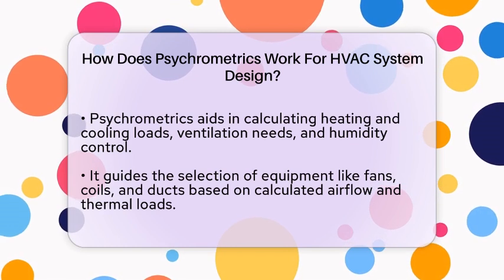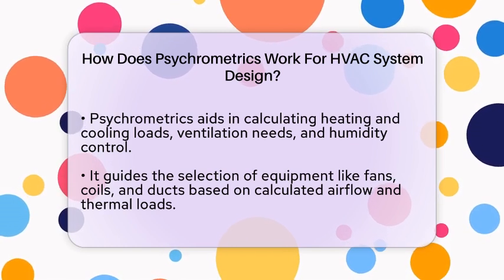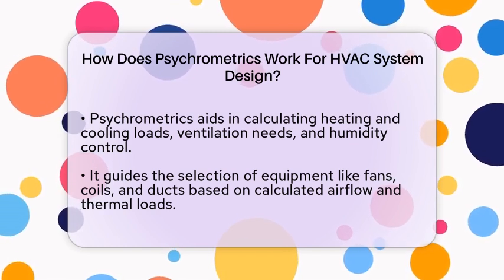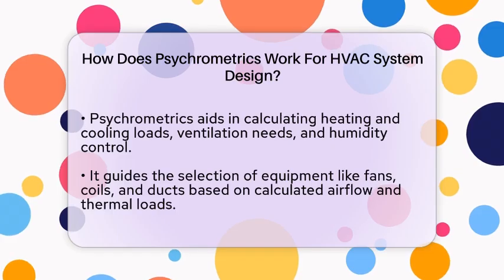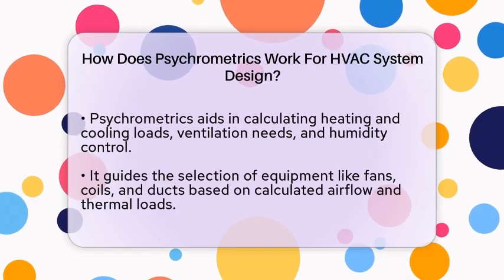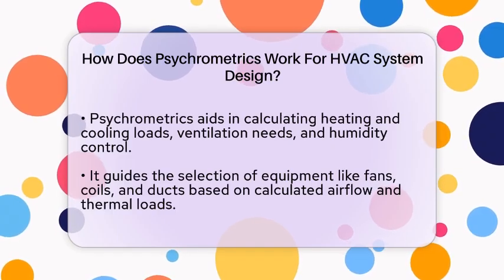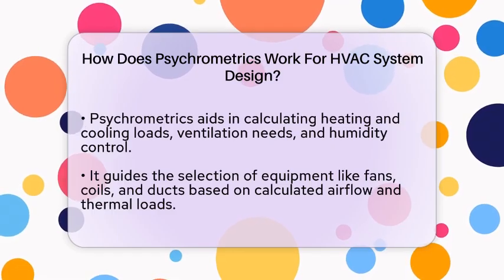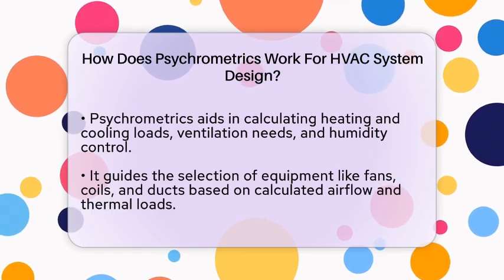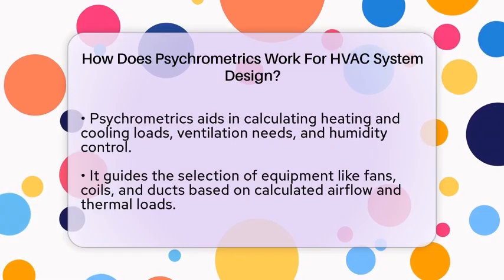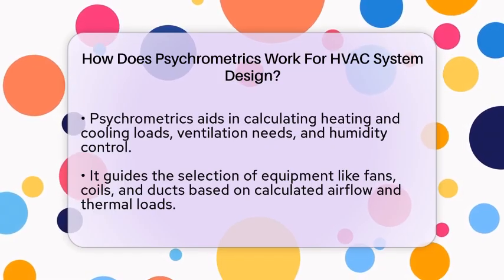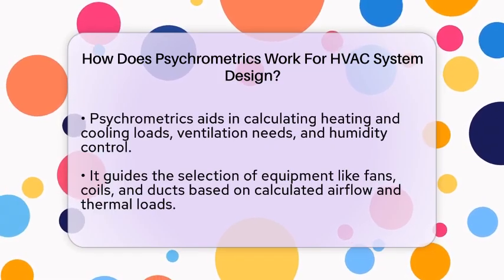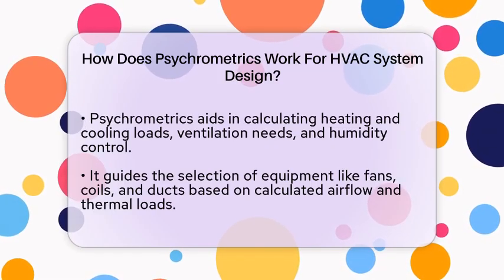In practical terms, psychrometrics allows engineers to convert thermal loads into airflow rates. If a space needs a certain amount of cooling, they can figure out how much air must flow through the system. This helps in choosing the right air handling units, fans, and duct sizes. It also ensures the mechanical room has enough space for all the equipment.